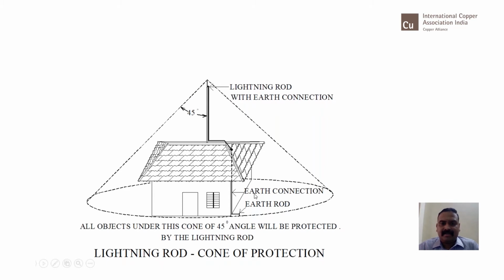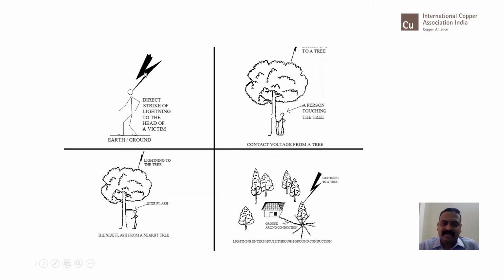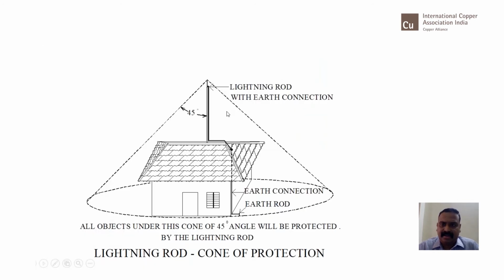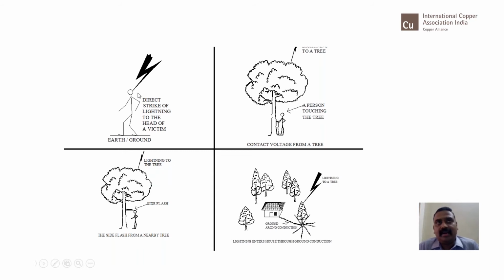Remember, this does not apply, because if there is a lightning strike, if you have this kind of vertical termination, only a lightning strike directly on the person can be avoided. However, there are fair chances that a person touching any metallic object or a tree nearby, or standing on the ground, will encounter a step potential, can encounter a touch potential, or even if there is an unsafe distance between the object and him, there is a chance that a spark-over can happen during this moment of lightning passing through the conductive area.